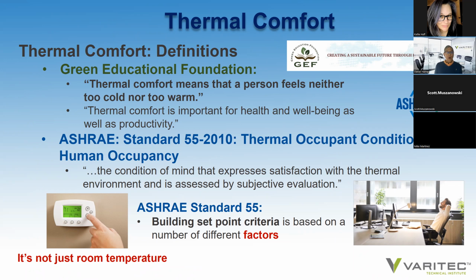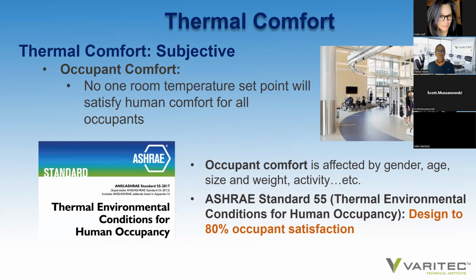Well, who defines the building set points to maintain thermal comfort? It's ASHRAE Standard 55, and they do so by taking various thermal comfort factors into mind. And we'll cover those shortly. So occupant comfort, how do we maintain thermal comfort in a space when you consider that everybody has a different body temperature. No two people are the same. We each have a different sense of what it is to be comfortable.